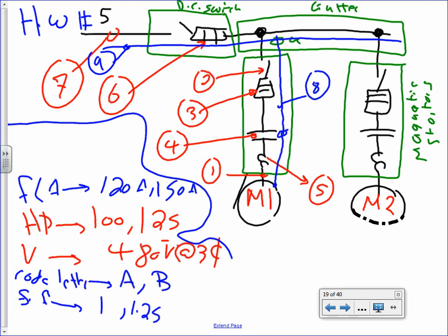And that's it, guys. This is the first and probably the last time you're going to hear Chad talk about this one, except I'm going to review for the test. My expectation is that later on, when you start doing branch circuits for all your equipment in Revit, your panels have to be filled with an overcurrent protection device and a conductor size. How are you going to come up with them? You take one motor at a time and do the calculation for it. With Revit, we care about two things: the overcurrent protection device and the branch circuit size. We're going to be collecting the OCP for every single motor in Revit.